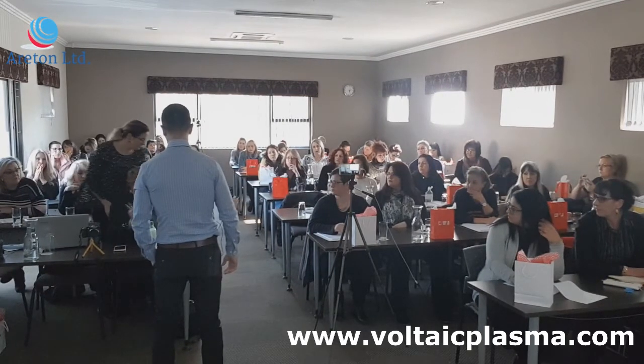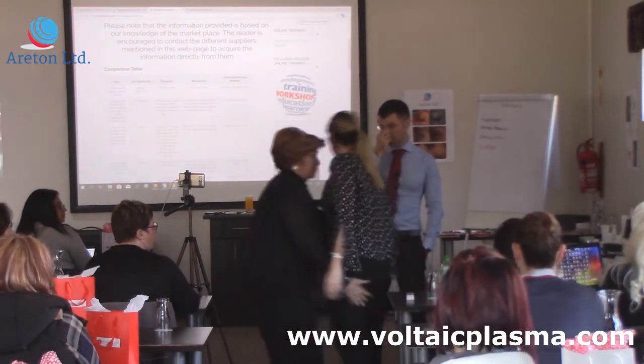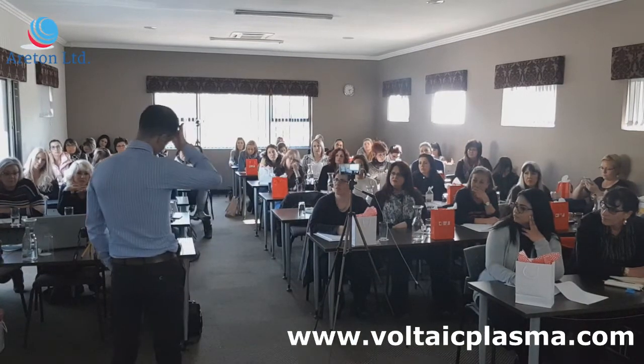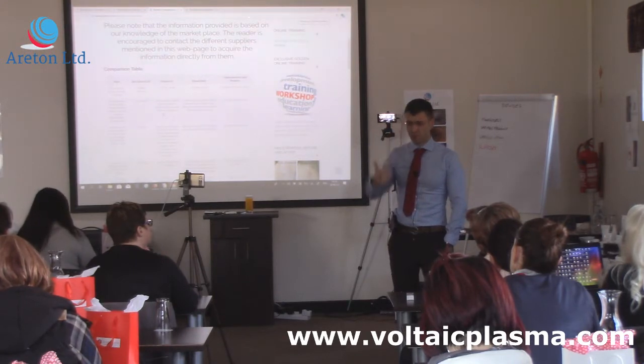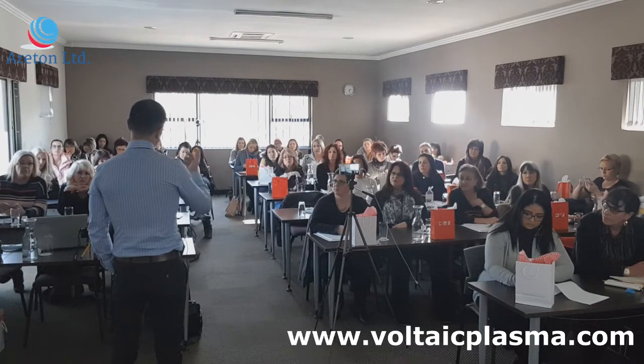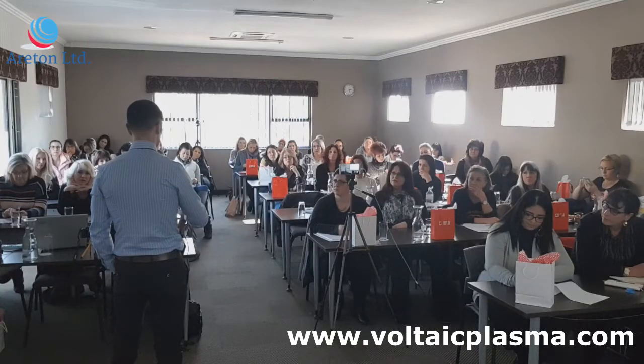So can you talk to us now about using the orange or the blue pen? For that, yes. Now, I'll have to actually do some good trials on it, but it's got only 2 power levels. I'll try it hopefully tomorrow or after tomorrow. But the point is, first of all, you want to do the practice on the test meat. So you want to be able to generate the arc quite comfortably. And depending on how the device is set up, you want to start at the highest power setting so you know how to generate the arc, and then be able to generate the arc at the lowest power setting.